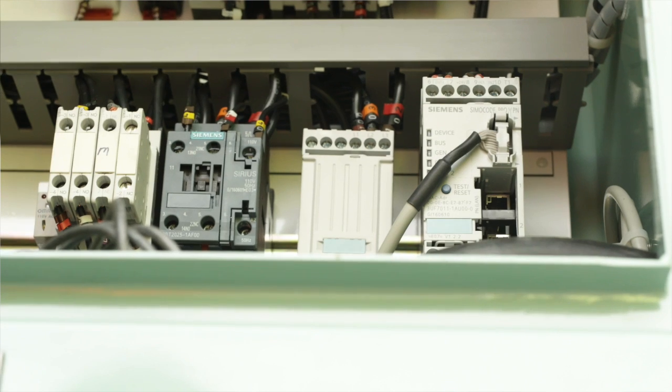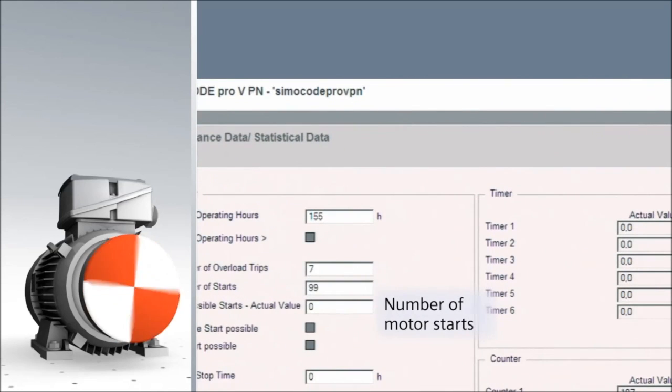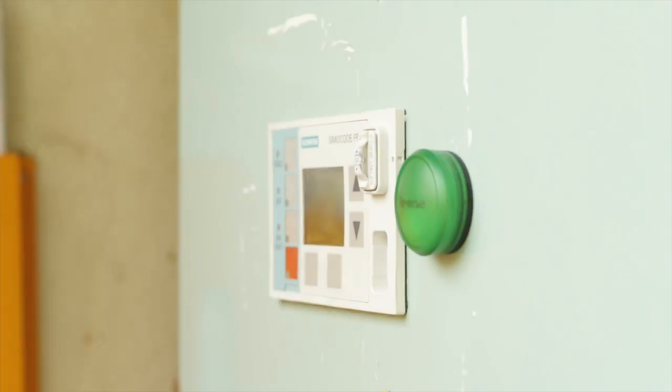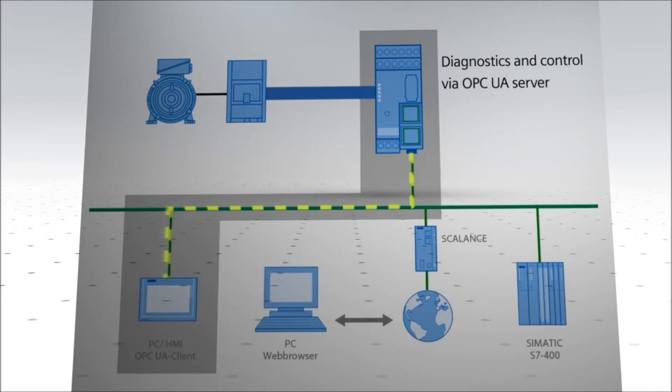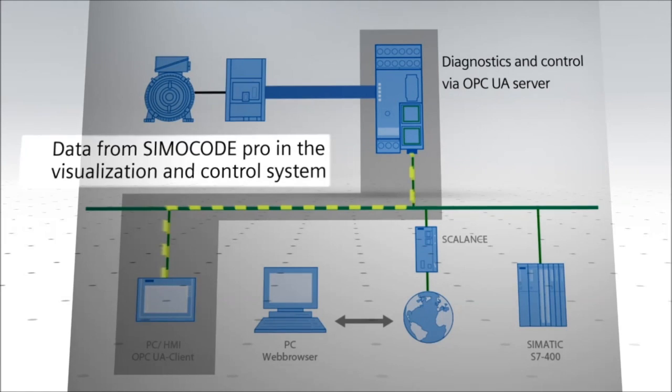Going further, we took a proactive approach, which was more to do with energy saving. It operates based on the number of starts, and what it's trying to do is stop a small problem from becoming a big problem. What we've seen on the actual installs is a 70% decrease in blockages on site. It's not very often that such a complicated problem can be solved with such a simple product as SIMOCODE. It's relatively simple to deploy — there's no PC or software tools to learn. Moving forwards, it provides a secure internet connection so that management can look at the operational values associated with the pump.